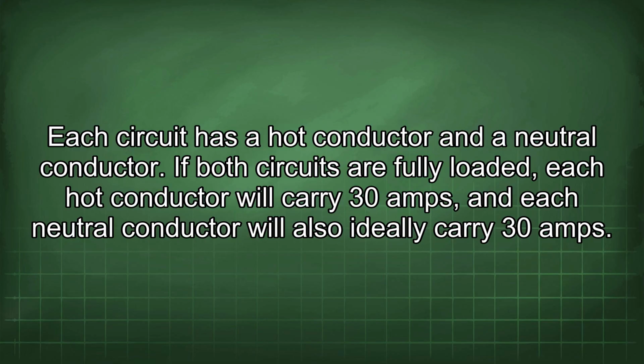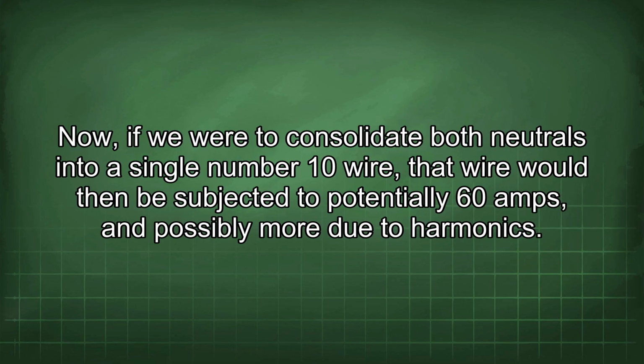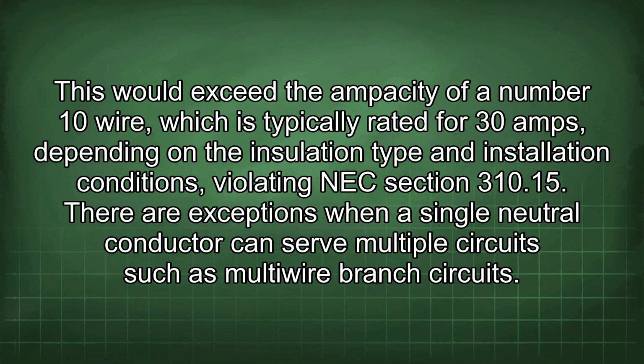carry 30 amps. Now, if we were to consolidate both neutrals into a single number 10 wire, that wire would then be subjected to potentially 60 amps, and possibly more due to harmonics. This would exceed the ampacity of a number 10 wire, which is typically rated for 30 amps, depending on the insulation type and installation conditions, violating NEC section 310.15.